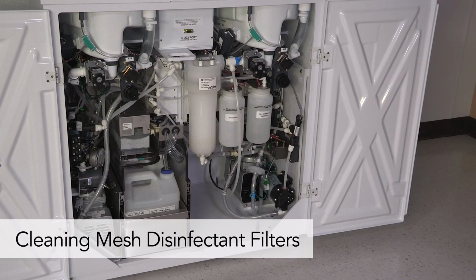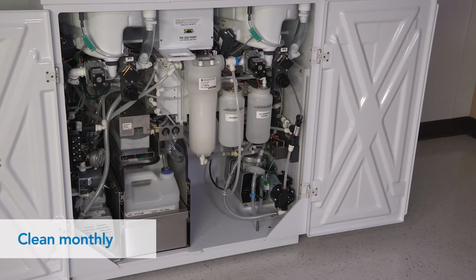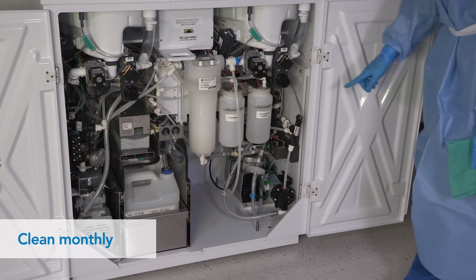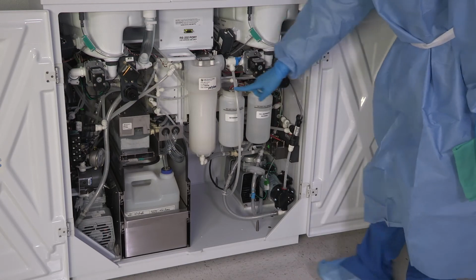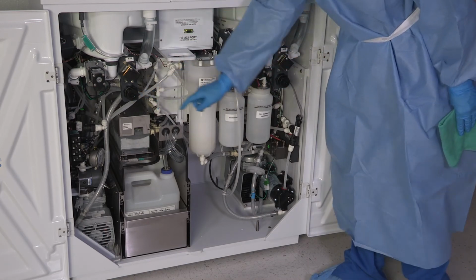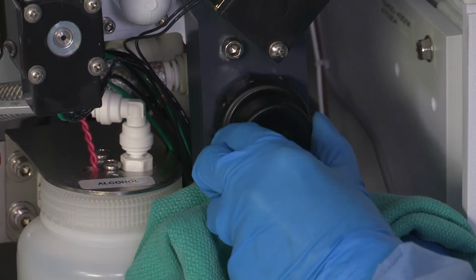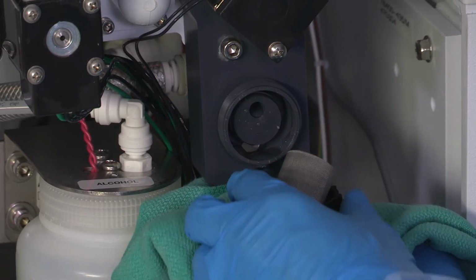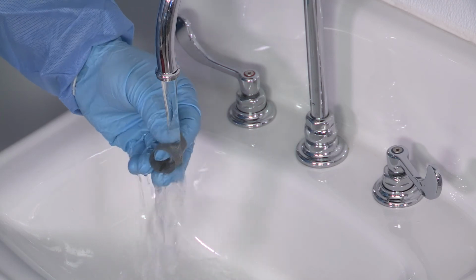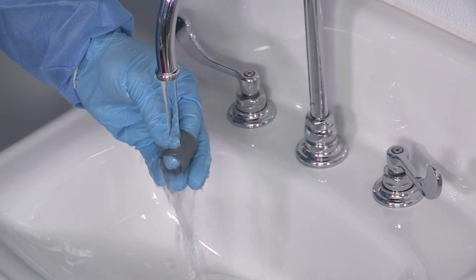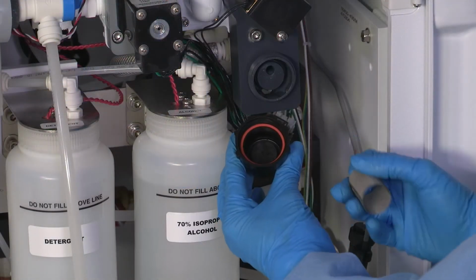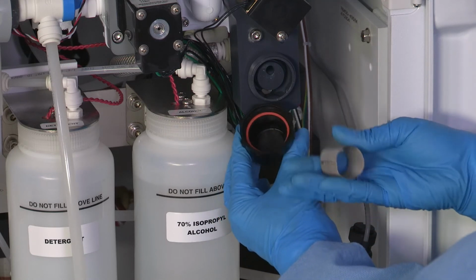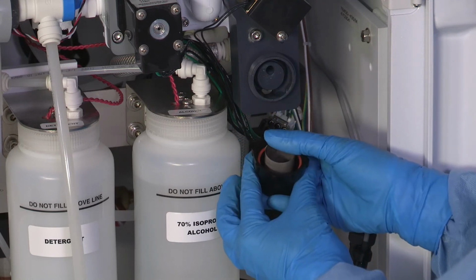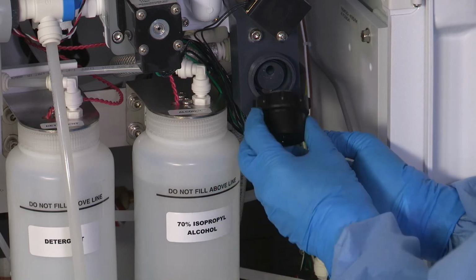The DSD EDGE Reprocessor has 2 reusable mesh disinfectant filters that need to be cleaned on a monthly basis. They are located inside the cabinet, under each basin, inside the black cap. To remove the filter, twist the cap off. Pull the filter out and clean by removing any lint and rinsing under clean water. Ensure the O-ring is in the groove of the cap to prevent leaking. Reattach the cap.